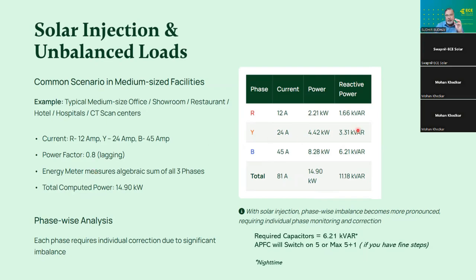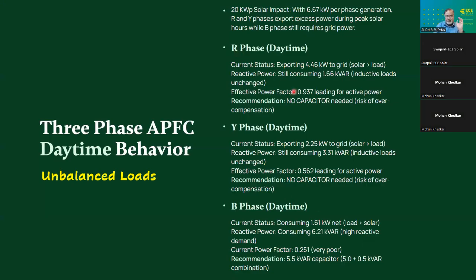Coming to reactive power compensation. Reactive power compensation required in R phase is only 1.66, Y is only 3.31, and B is 6.21. Now, as we have seen in the logic flow chart of the APFC panel, the capacitor will try and compensate the maximum. That means 6.21 kVAR. The three-phase APFC will try and compensate 6.21 kVAR. Now it will switch on 5, or if it is a fine-tuned APFC, maybe they will have 1 kVAR as one step also. It will switch on 6 kVAR. Fine. So what happens as a result? R phase is overcompensated. There is actually no capacitor required. It is going in an export mode. We are exporting reactive power. Same is the case with Y phase. No capacitors are needed for this phase, and B phase is happy.